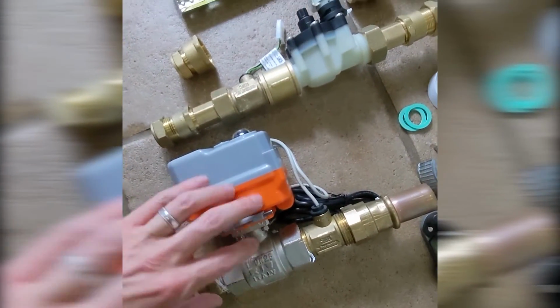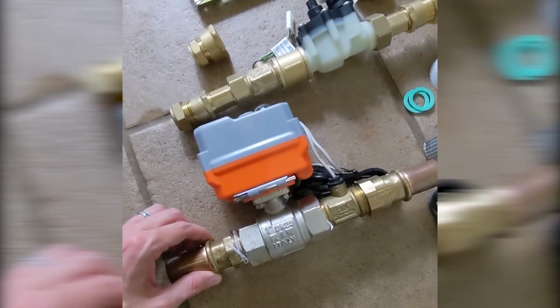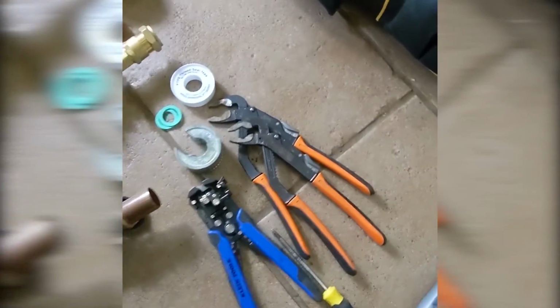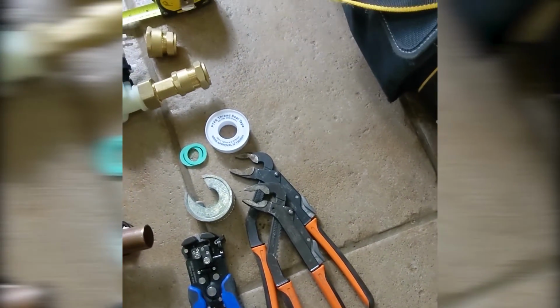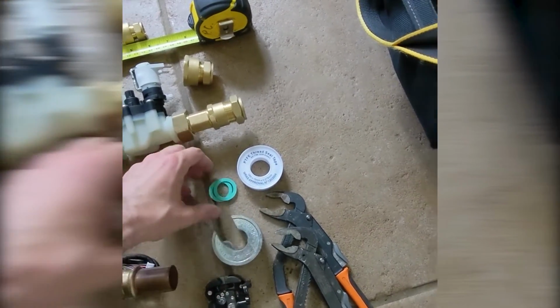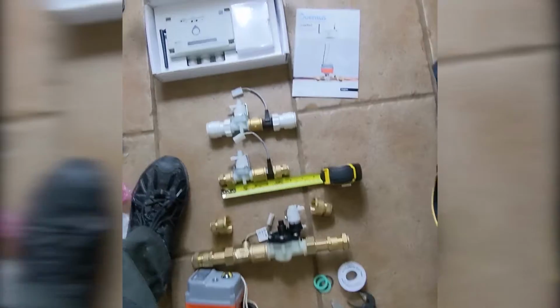Everything's hand tightened there with some washers in the middle. For the bigger pipes, we use motorized valves with flow sensors. On this build up here, we've got press fit fittings going on to 28mm copper. So the tools that you need for this are 2 wrenches, a wire stripper, pipe cutter, and PTFE tape or washers. For the larger pipe, you'll need some hacksaws, but for now it's quite simple. Once these are plumbed in, we'll then cable this all up to the LeakNet base unit and connect it up.